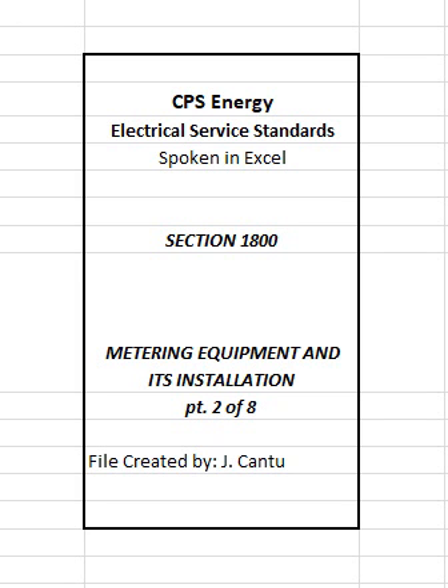CPS Energy will utilize demand diversification to customers' calculated loads when sizing transsockets. Transsockets may accommodate estimated demand loads up to 800 amperes and service conductor sizes up to 2 to 500 kcm cables per phase. Standard instrument transformer enclosures may be installed on an exception basis for estimated demand loads of 800 amps or less if requested by customer. CPS Energy furnishes the following standard transsocket enclosures for installation by the customer.